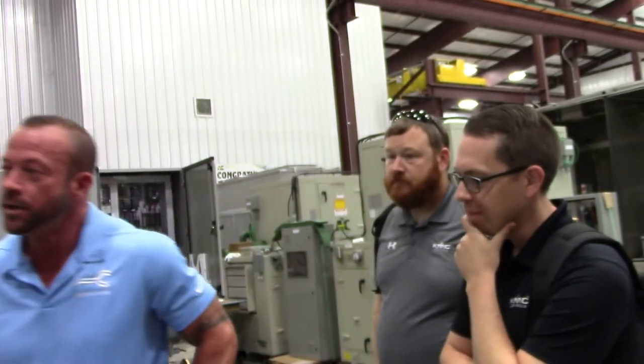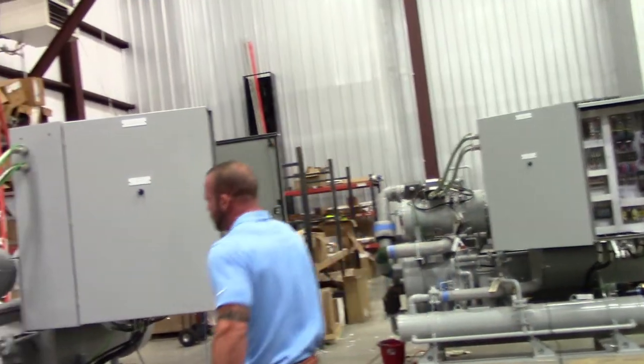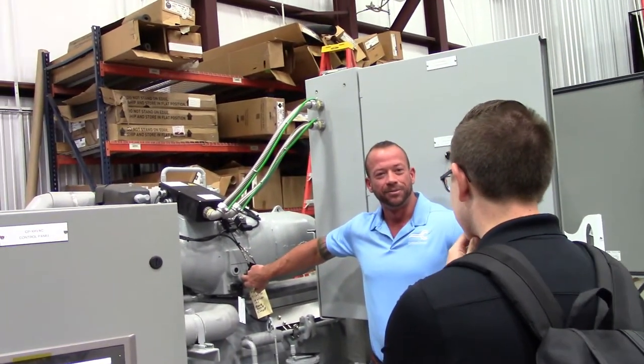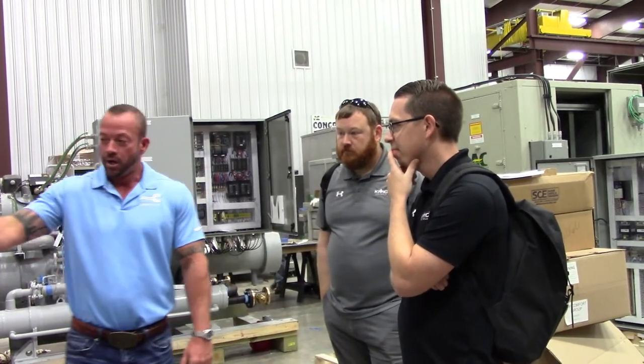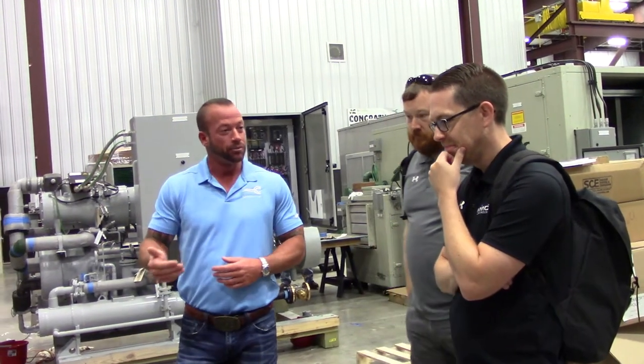All the transducers are zero to 10. We monitor all the high pressure, low pressure, and suction pressure. We even have an oil monitor that goes on the sight glass — there are two sight glasses — so it actually monitors the oil level in the sight glass. It's all going back to our KMC Controls. KMC controls are monitoring all the pressures, all the temperatures, oil level. If any of that is out of range, we alarm and generate alarms into the control room. An alarm pops up on the HMI so the operators know what they're looking at when they come out.